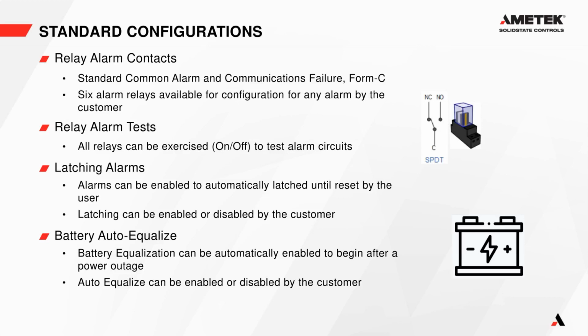And then we also have a user configurable battery auto equalize function. This will put your battery into auto equalize mode after a power outage of 5 minutes or longer. This does require the battery connection, so that the display will know how long the system has been without power.